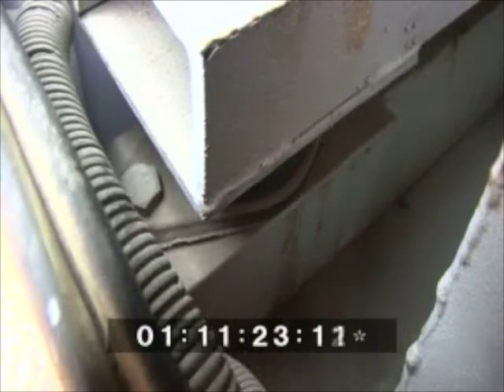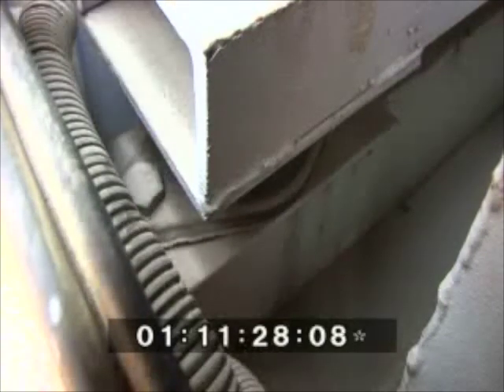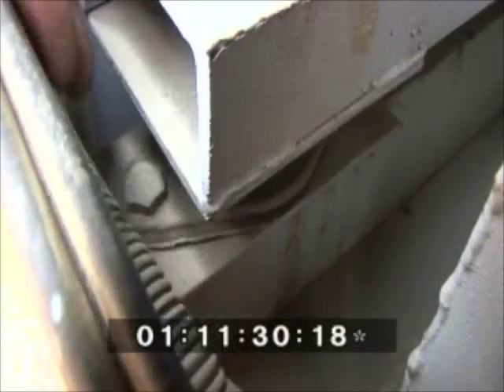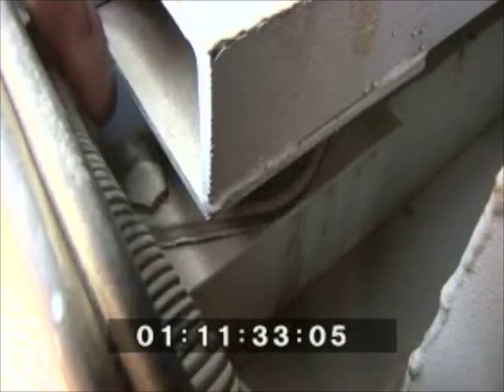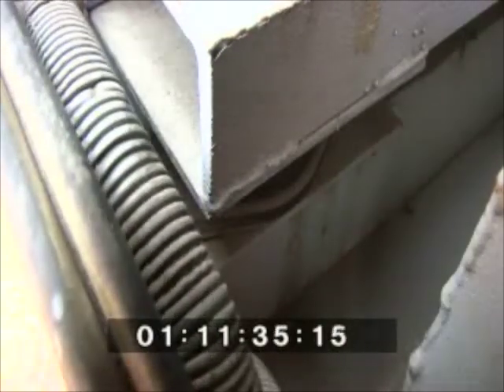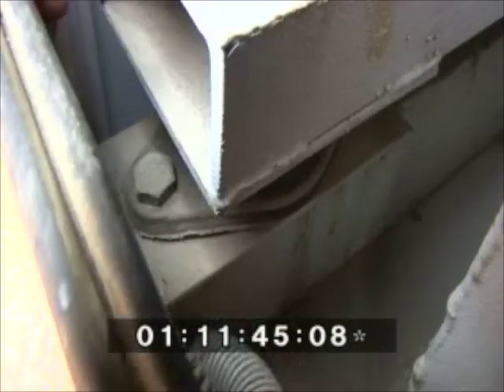Now, we will check for vibration of the DG. At the base of the DG, inside the canopy, you can see the AVM, that is, the anti-vibration pad. It reduces the vibration of the DG. In case the DG is not mounted properly or the AVM pad is damaged, the DG will start vibrating more.